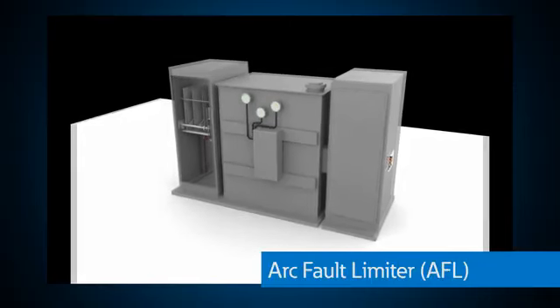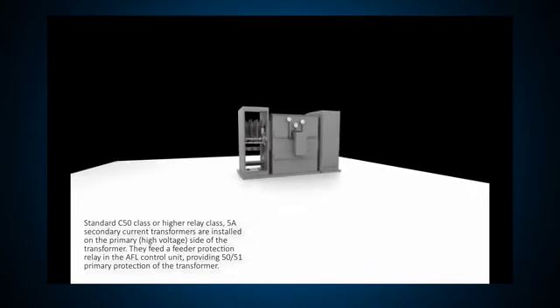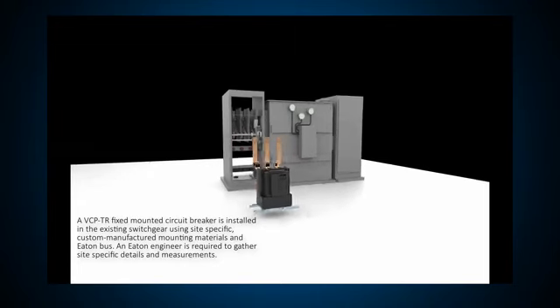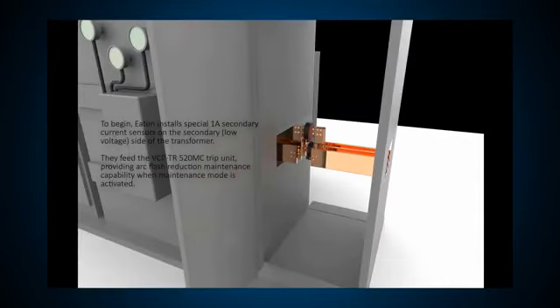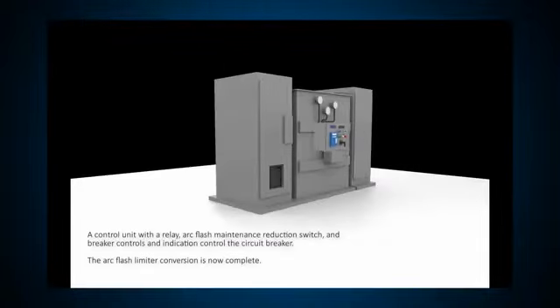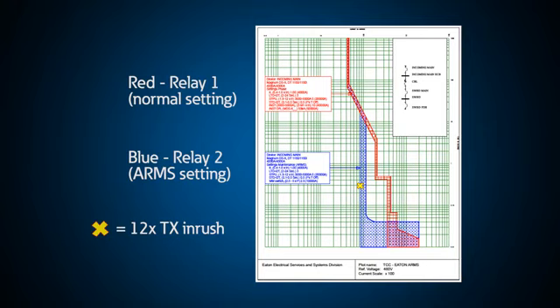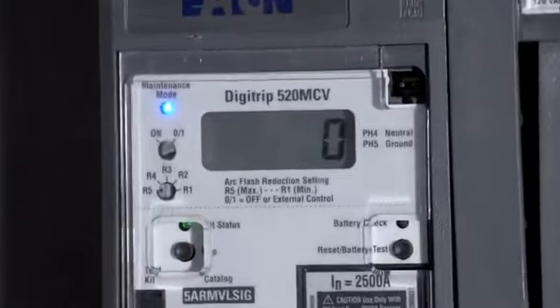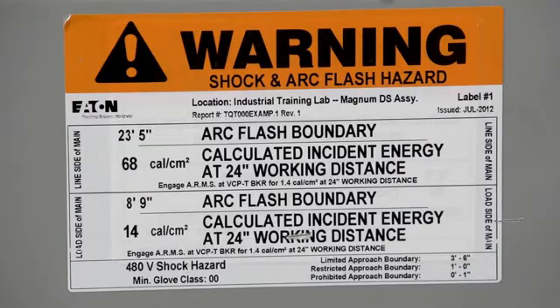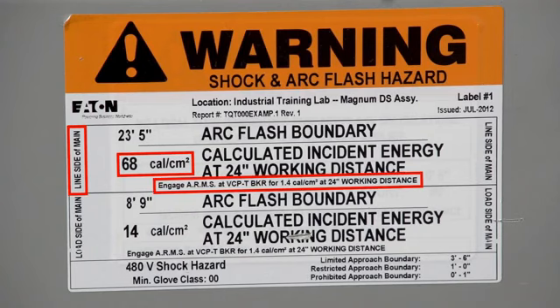One great option we can show you here at the PSEC is the arc fault limiter, or AFL conversion. For this demonstration, we have replaced the typical medium voltage primary fuses protecting this transformer with a medium voltage vacuum circuit breaker, and we installed current transformers, or CTs, on the secondary of the transformer and added another protective relay. Since the breaker has two protective devices that can trip it, one is set as it normally would to overcome the 12 times inrush current for the transformer, and the other is connected to the transformer's secondary CTs. Using an ARMS setting on the medium voltage breaker, it will trip without delay during a fault condition. This arc flash label indicates that the arc flash energy at the line side of the breaker is normally 68 calories. The AFL solution significantly reduces the arc flash energy to 1.4 calories during maintenance conditions.